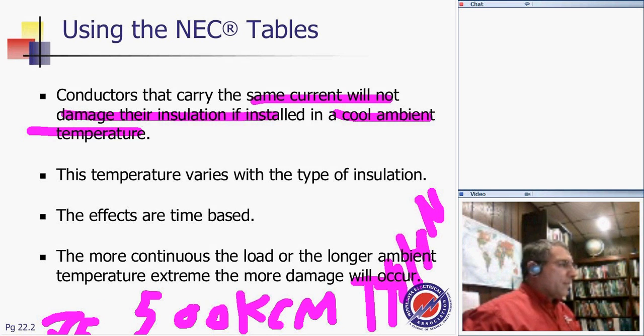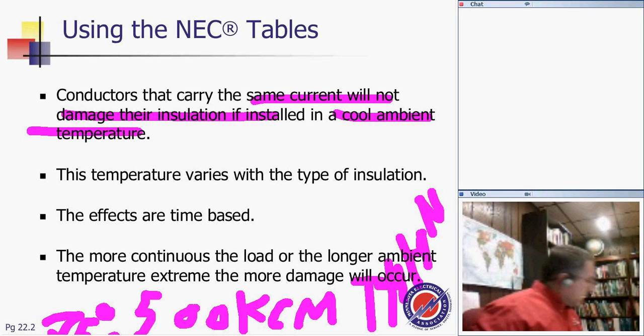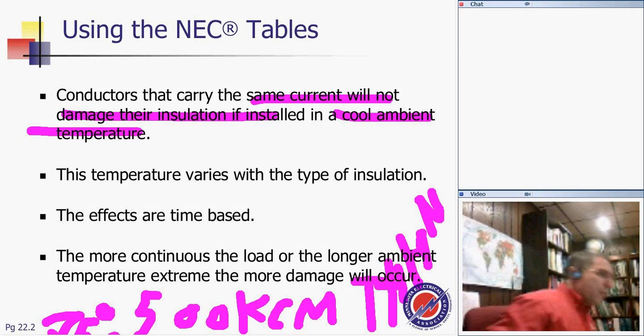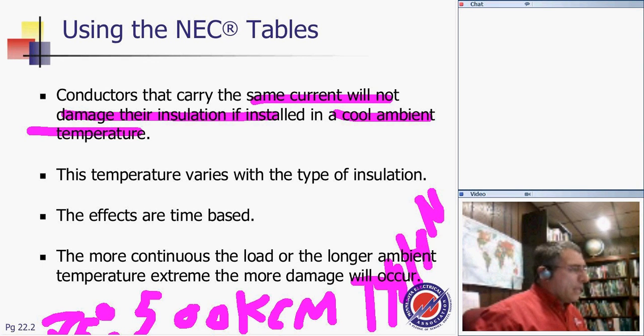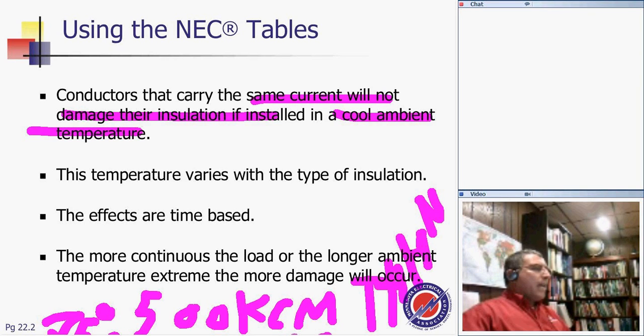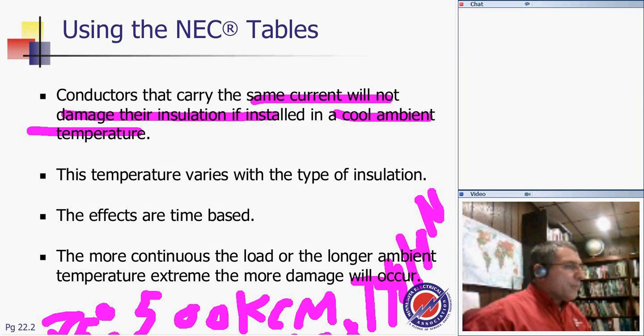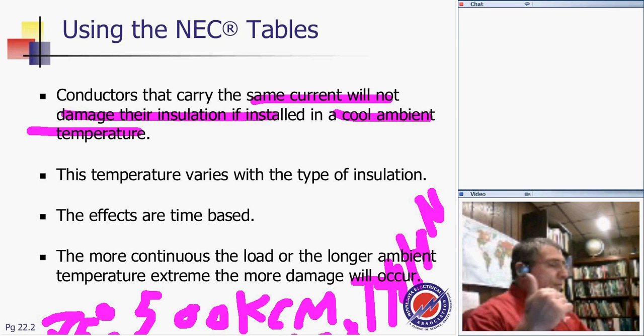Look how specific the degree Celsius is for the lug. Then in a case like this, I'm sure you guys will come and say, "Oh, we know that for a fact, it's 380 amps." Can you get 380 amps? For a 500 kcmil conductor to carry 380 amps, first it has to be in an ambient temperature of 30, and the lugs have to be 75. Then the conductor can carry 380 amps. So you see how much current a conductor can carry, guys. You have to state the circumstances for that particular conductor.